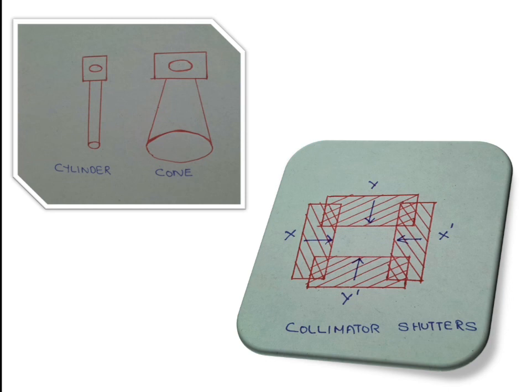The area of exposure is determined based on the body part being examined. For a hand x-ray we need a smaller area; for a finger it decreases further; for a chest x-ray the area will be larger; and for an abdomen x-ray the area is larger still. Using the collimator light, we can see how much area will be exposed and adjust the shutters accordingly to expose only the required area.